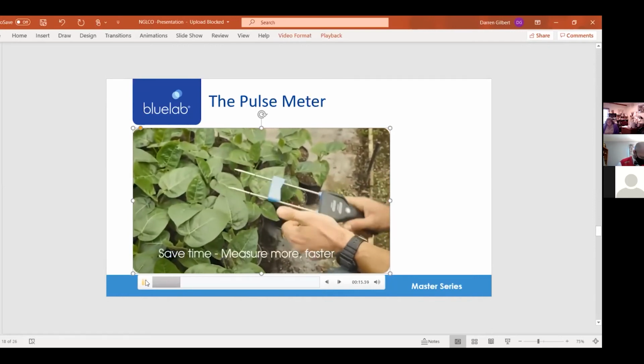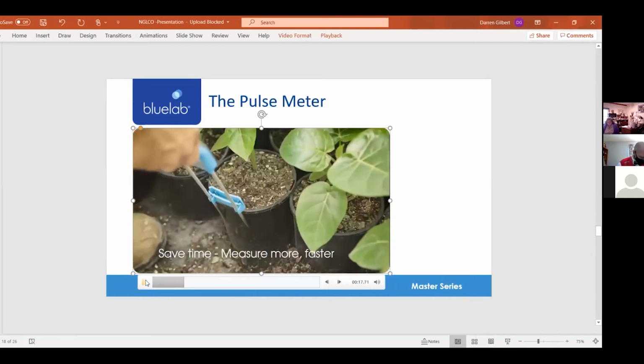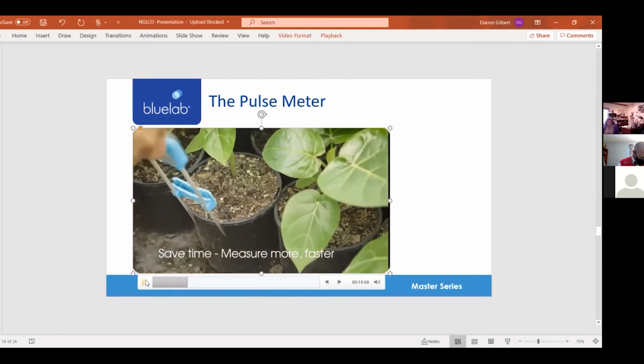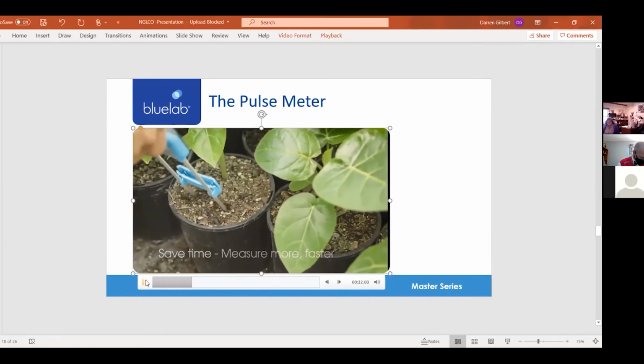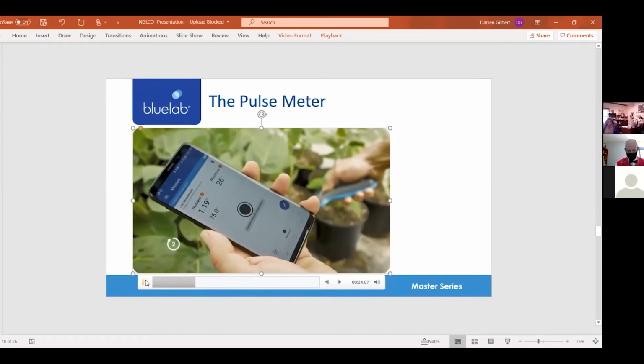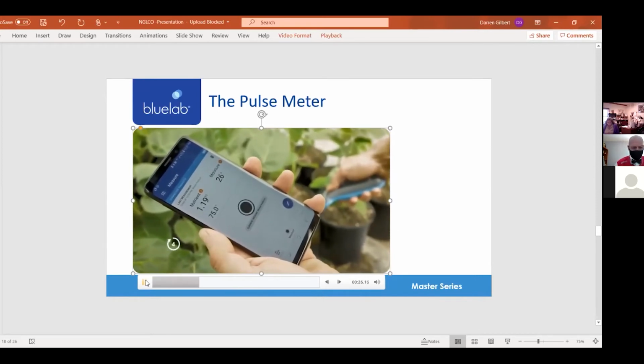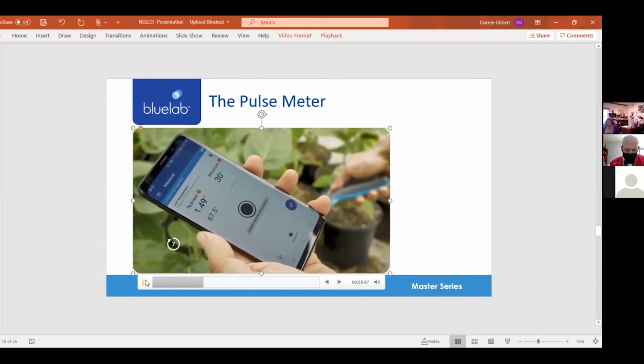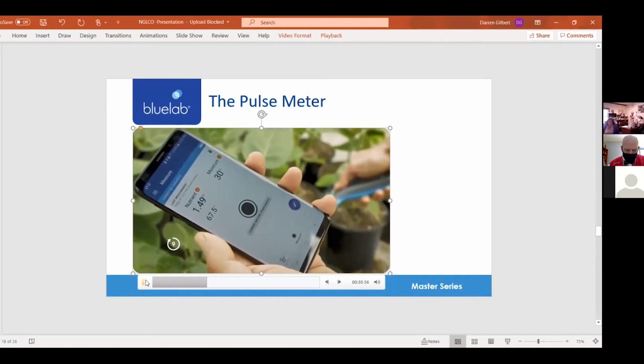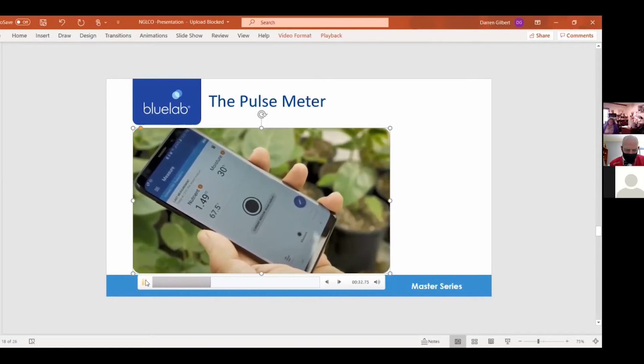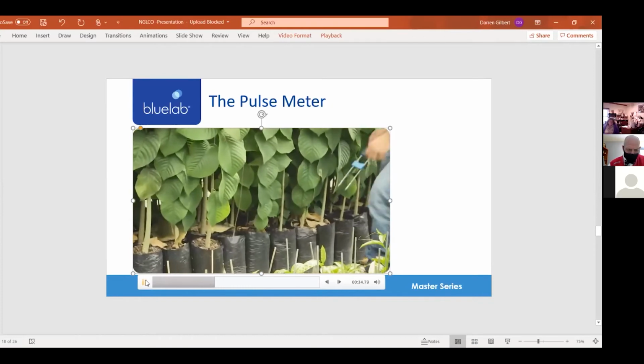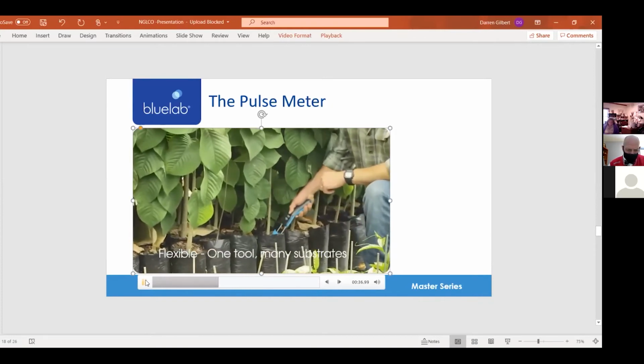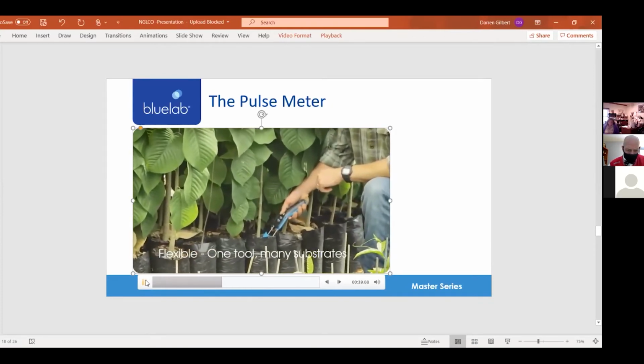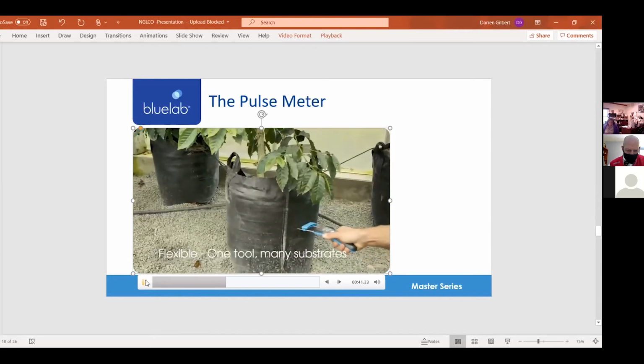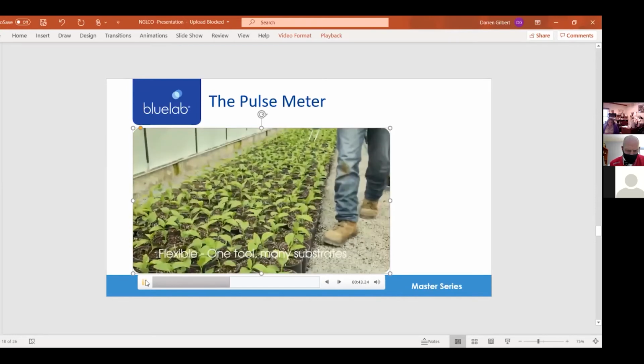That slide gauge, as we call it, on the device allows you to find the center of the container and get consistent readings on each pot. So if you're always doing an 8-inch pot, you always want to be about 4 inches down and 4 inches in from the outer edge, and this way you'll get a consistent, accurate reading as you take those measurements. You can snap that off altogether if you want to go into a bigger pot, or if you want to go in from the side, you can do that as well.